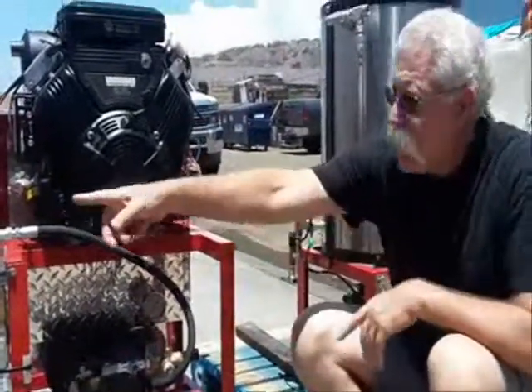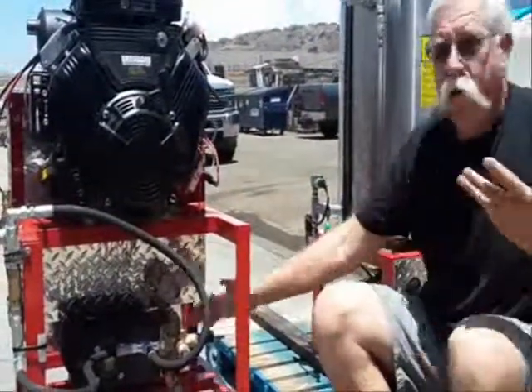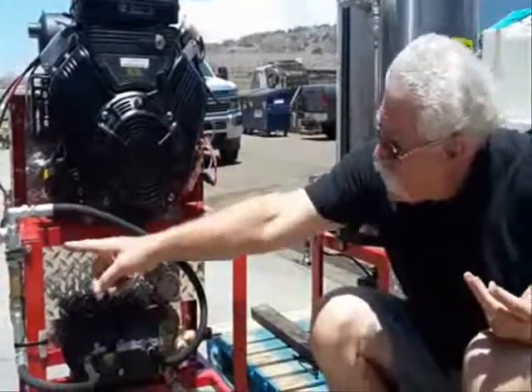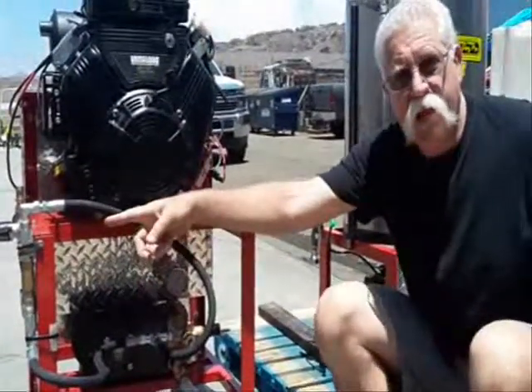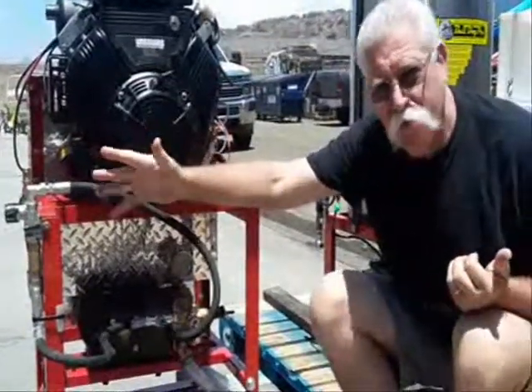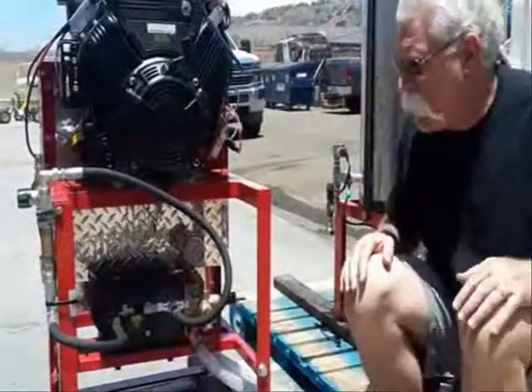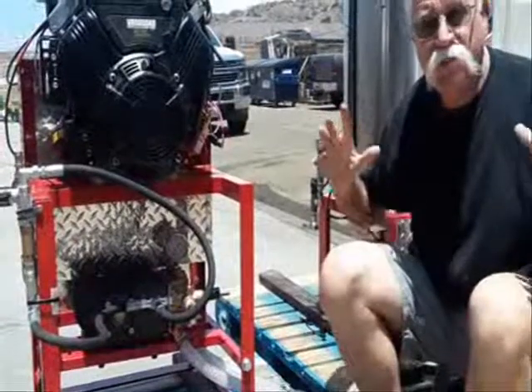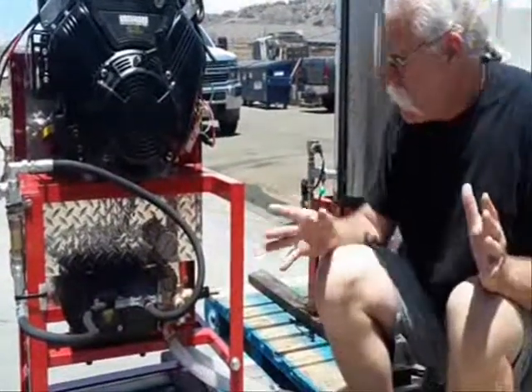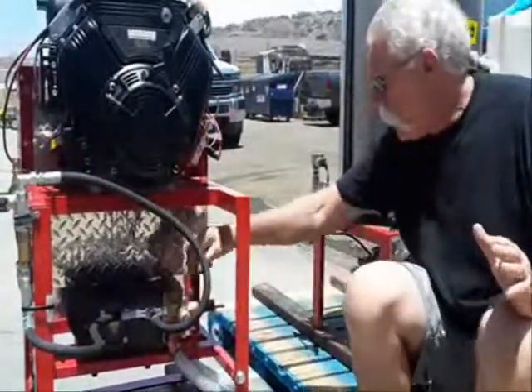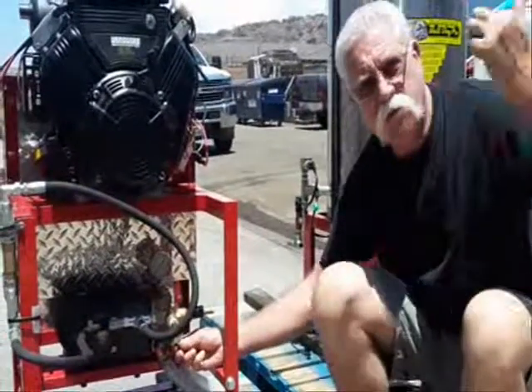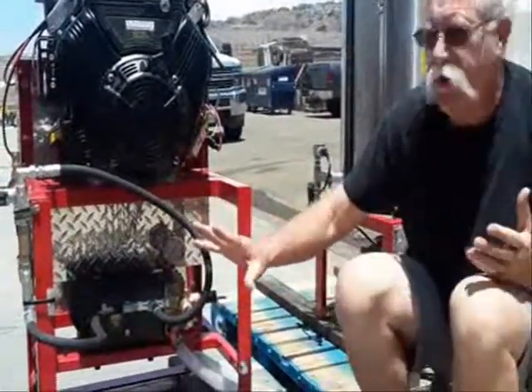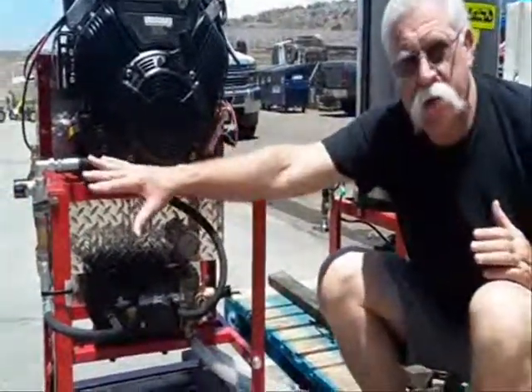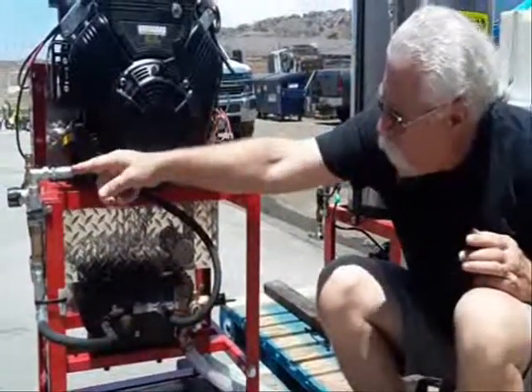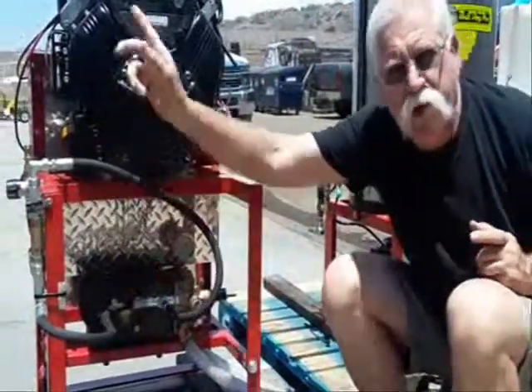If you've got that valve closed and we're supposed to be making full pressure and that unloader is bypassing back to the tank, you know that this valve is bad and it's not closing all the way. So think about the functionality in how you're setting the system up to begin with. You've got your primary unloader. It's going to have a bypass line here going back to the holding tank. And if we're going to also use the secondary regulator, then that valve's going to be open and some of the water is going to be bypassing back to the holding tank.